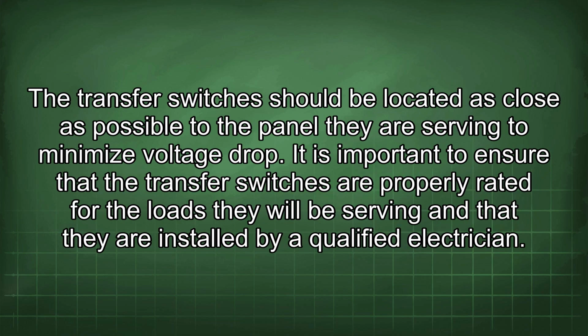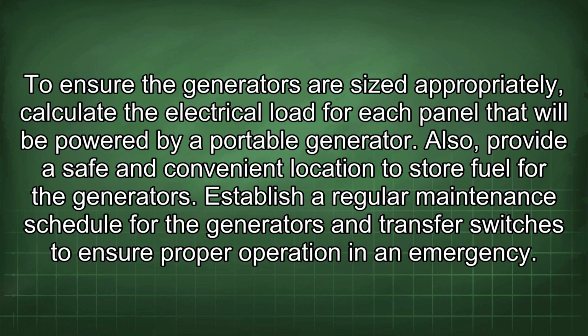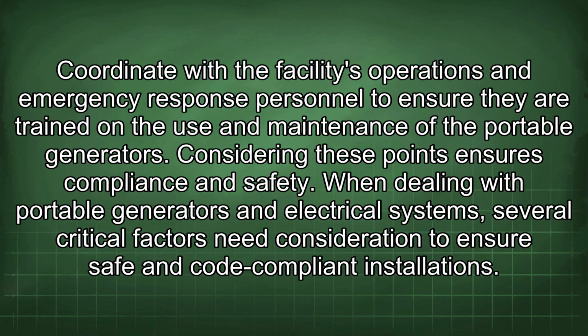The transfer switches should be located as close as possible to the panel they are serving to minimize voltage drop. It is important to ensure that the transfer switches are properly rated for the loads they will be serving and that they are installed by a qualified electrician. To ensure the generators are sized appropriately, calculate the electrical load for each panel that will be powered by a portable generator. Also, provide a safe and convenient location to store fuel for the generators. Establish a regular maintenance schedule for the generators and transfer switches to ensure proper operation in an emergency. Coordinate with the facility's operations and emergency response personnel to ensure they are trained on the use and maintenance of the portable generators. Considering these points ensures compliance and safety.